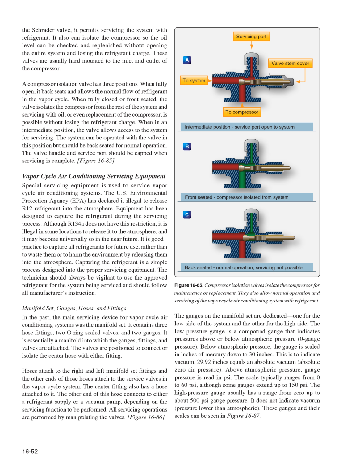Figure 16-86, servicing of the vapor cycle air conditioning system with refrigerant. The gauges on the manifold set are dedicated, one for the low side of the system and the other for the high side. The low pressure gauge is a compound gauge that indicates pressures above or below atmospheric pressure, zero gauge pressure. Below atmospheric pressure, the gauge is scaled in inches of mercury down to 30 inches. This is to indicate vacuum. 29.92 inches equals an absolute vacuum, absolute zero air pressure. Above atmospheric pressure, gauge pressure is read in psi.